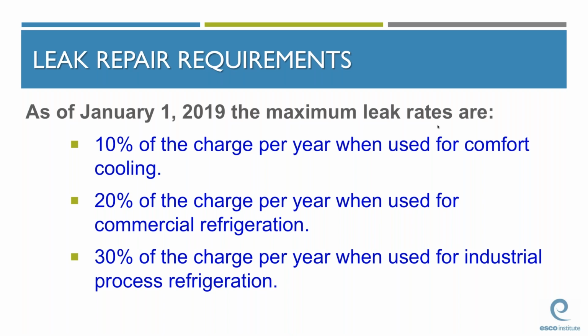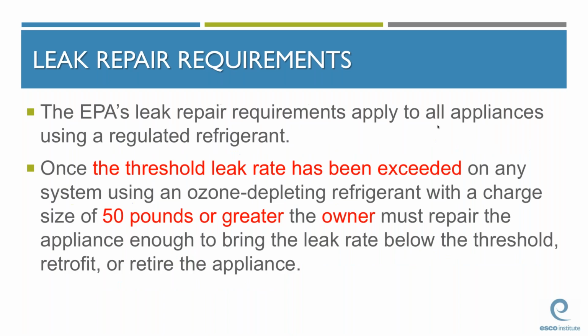The maximum allowable leak rates have changed effective January 1, 2019. The old 15% and 35% leak rates are gone. The new leak rates are based on the system classification. So for comfort cooling equipment, the maximum allowable annual leak rate is 10% of the system charge. For commercial refrigeration equipment, the maximum annual leak rate is 20% of the system charge. And for industrial process refrigeration systems, or IPR, the maximum allowable annual leak rate is 30% of the total charge.